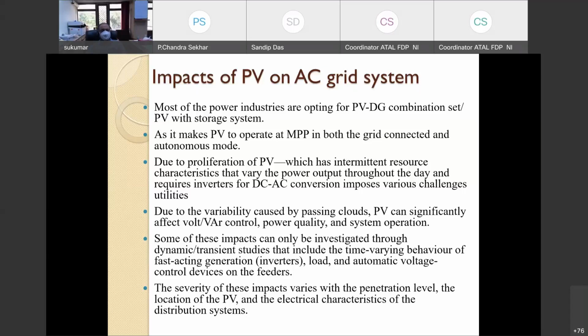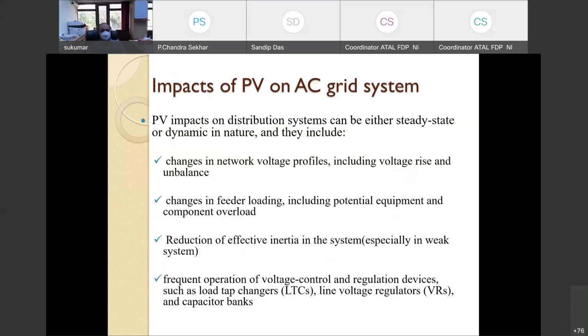Because of that, we can see here that the voltage will rise, and to handle the voltage rise phenomenon, we have to go for the tap changing operation of the transformer. While going for tap changing operation of the transformer, you will face that the transformer life will be jeopardized. Besides that, the inertia of the system also will reduce, because there is no rotating part involved in the photovoltaic system. And because the inertia will reduce, we will be in trouble with frequency variation when these inverters are being integrated with rotating machines.